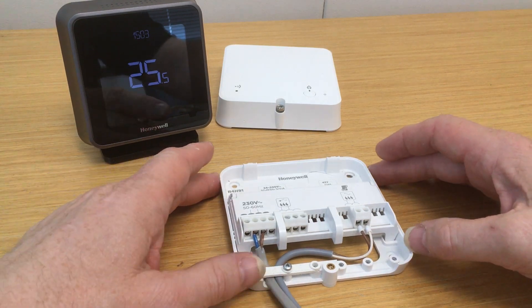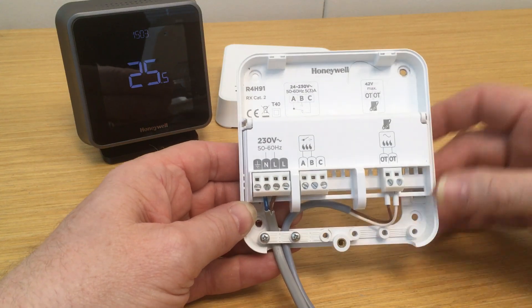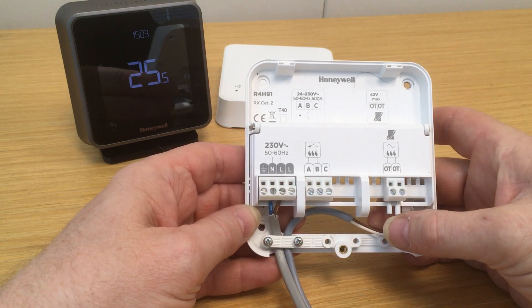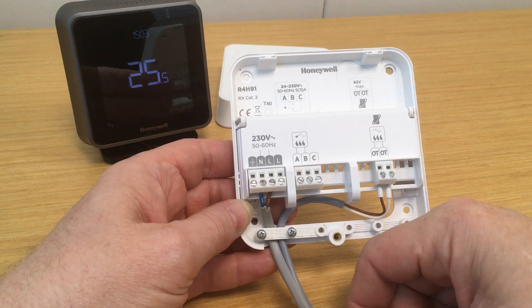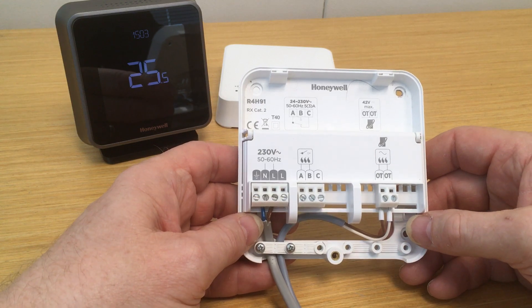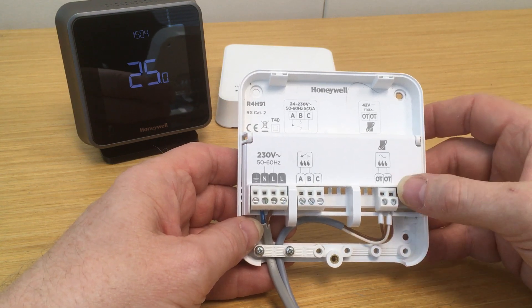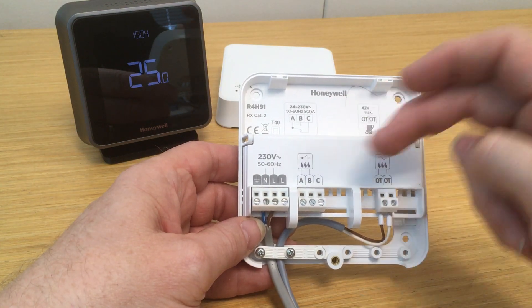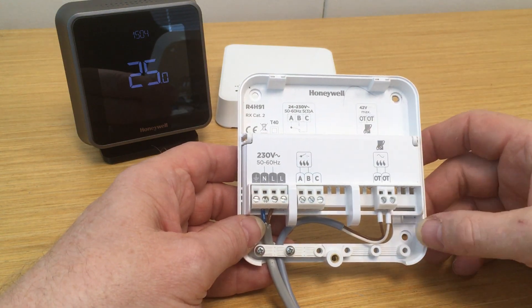So first of all, let's look at the wiring. Here is the base plate of the relay electronics module. First of all, we require permanent live and neutral connection here as marked. And then here we have the two OpenTherm terminal connections as marked. This is a two-core cable wired directly back to the OpenTherm terminal connections on the boiler. Consult your boiler manufacturer's instructions to identify the correct terminals to use on your particular boiler.